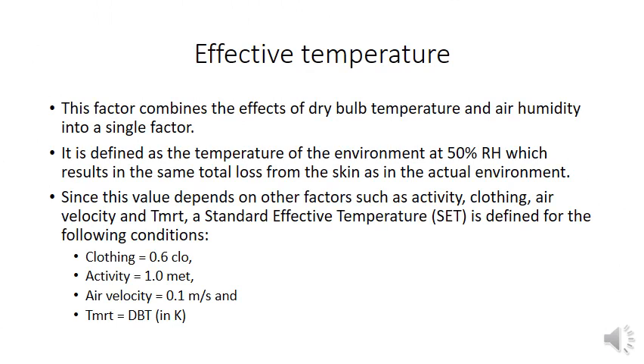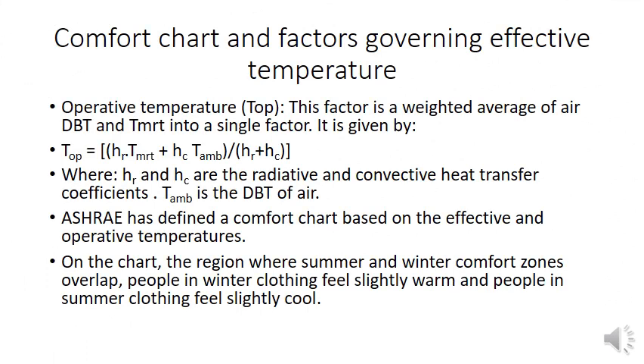Effective temperature is a single parameter that combines the effect of dry bulb temperature and air humidity. It defines the temperature at which an environment at 50% RH produces the same total heat loss from the skin as in the actual environment. Its value depends on activity, clothing, air velocity, and mean radiant temperature (TMRT). The Standard Effective Temperature (SET or ET*) uses clothing of 0.6 clo, activity of 1 met, air velocity of 0.1 m/s, and the dry bulb temperature. The operative temperature is the weighted average of air dry bulb temperature and TMRT using radiative and convective heat transfer coefficients.